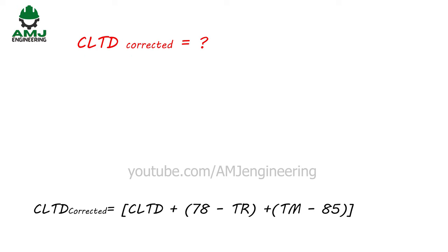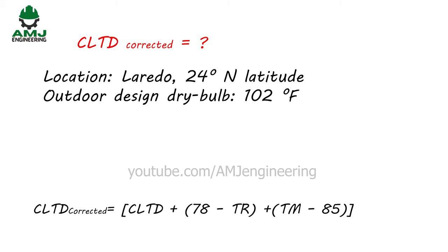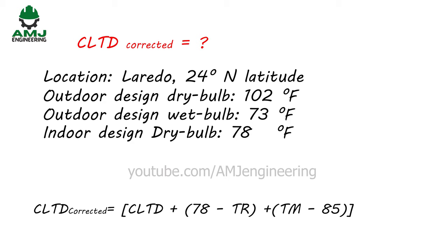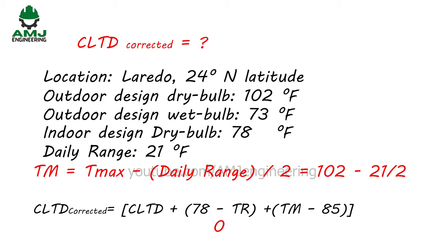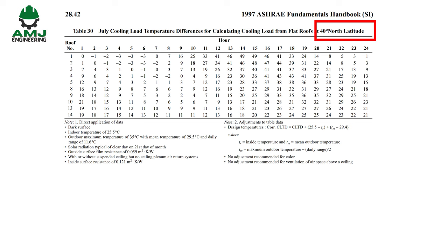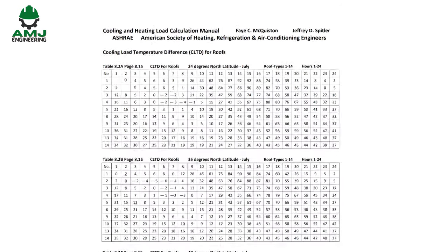Our first step is calculation of the CLTD correction using the given design conditions: Laredo at 24°N latitude; outdoor design dry bulb 102°F; outdoor design wet bulb 73°F; indoor design dry bulb 78°F; daily range 21°F. Since interior design temperature is 78°F, the term (78 − TR) = 0. TM = 102 − 21/2 = 91.5°F. Therefore CLTD_corrected = CLTD + 6.5. Note that the ASHRAE 1997 handbook contains CLTD tables for July at 40°N latitude.